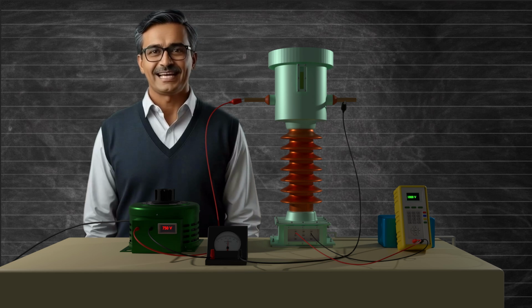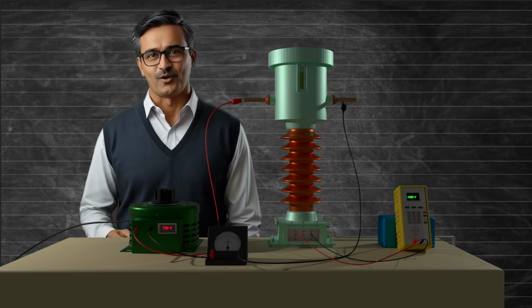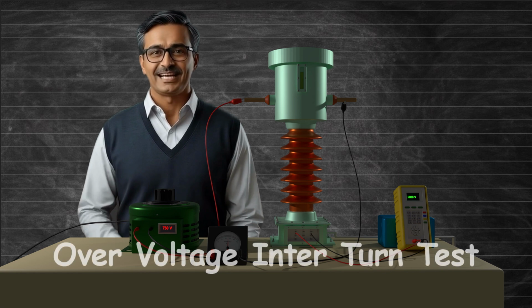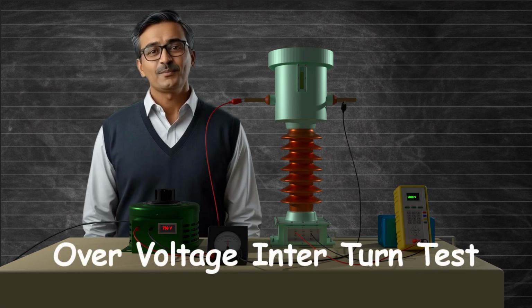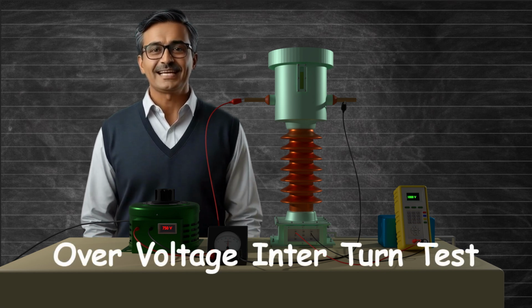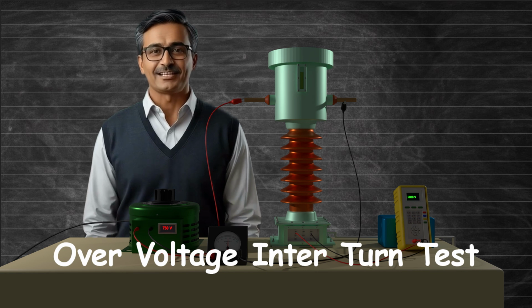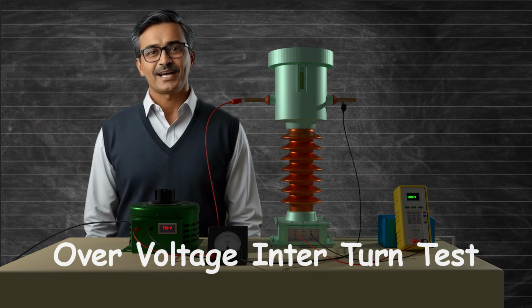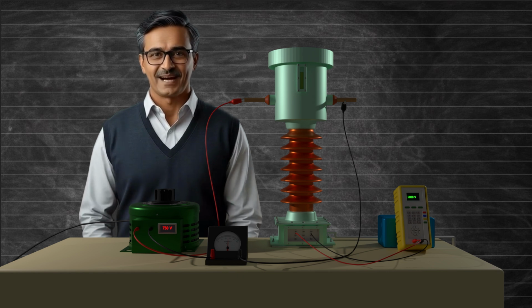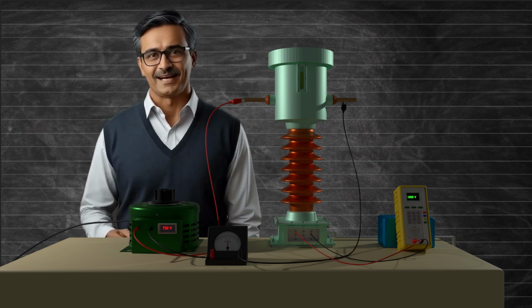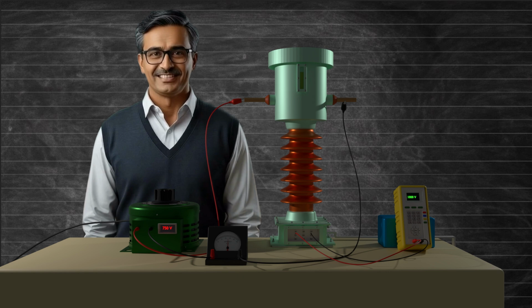Let us discuss the inter-turn overvoltage test, also known as the overvoltage inter-turn test on a current transformer. This test checks the insulation health between adjacent turns of the secondary winding of a current transformer. As per IS 2705, there are two simple methods to perform this test.